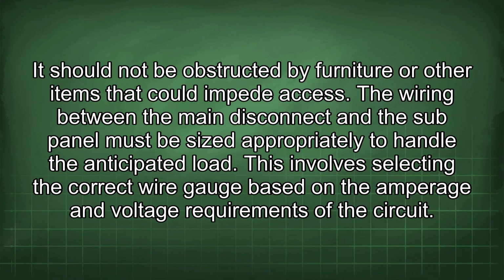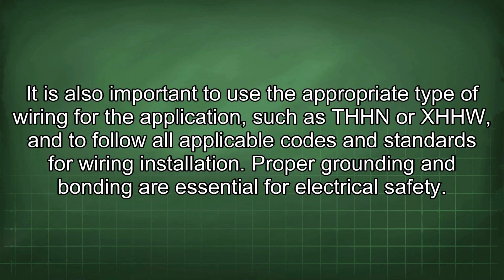The wiring between the main disconnect and the sub-panel must be sized appropriately to handle the anticipated load. This involves selecting the correct wire gauge based on the amperage and voltage requirements of the circuit. It is also important to use the appropriate type of wiring for the application, such as THHN or XHHW, and to follow all applicable codes and standards for wiring installation.